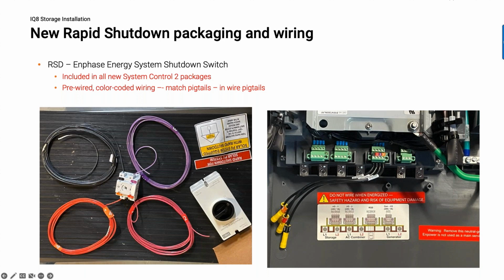Now, one other note about this is that we're actually closing two separate contacts. When you flip the switch to on, what happens is it's actually connecting two circuits. If you look at this header here, you can see my arrow. We've got 1, 2, 3, and 4. When you close the switch, it actually connects 1 and 2, and it connects 3 and 4. And that's the normal operating mode of the system. You want 1 and 2 to be connected and 3 and 4 to be connected. And what that does is that enables the system to work.